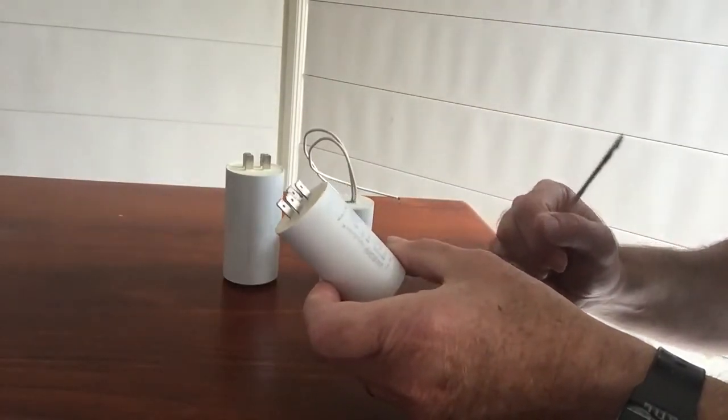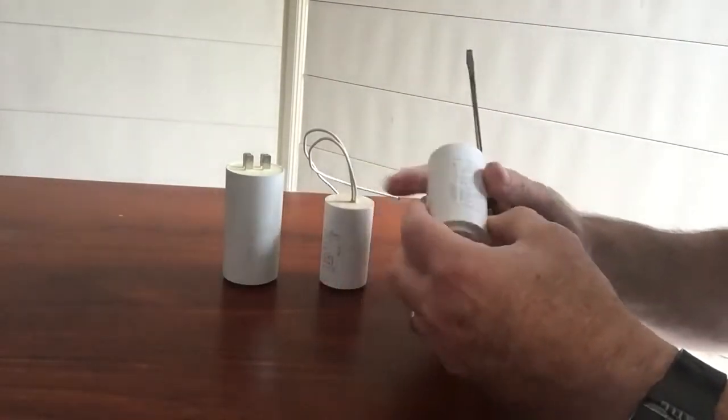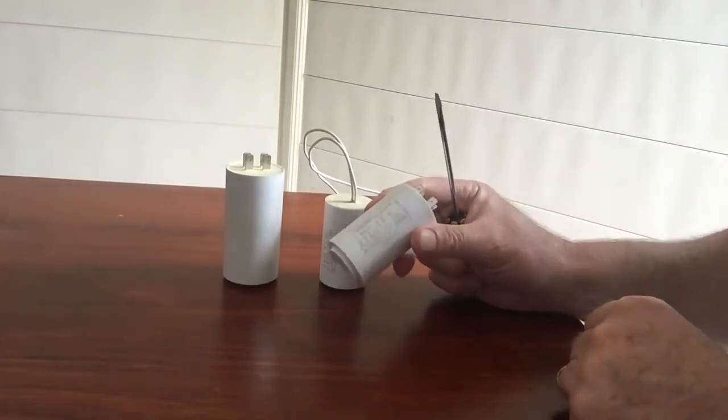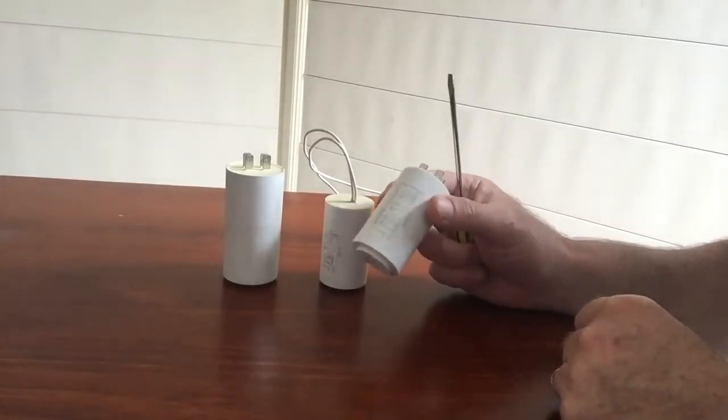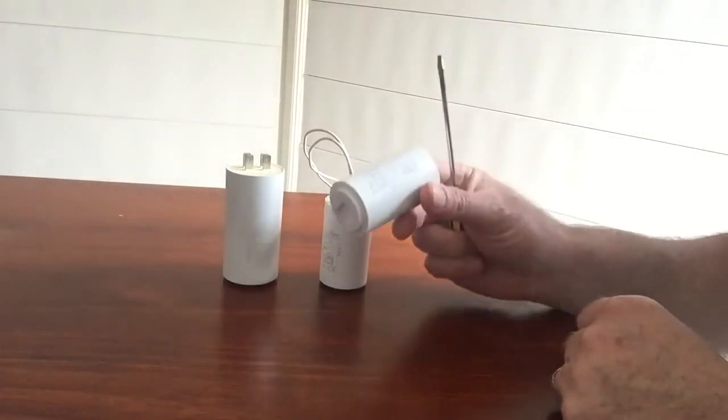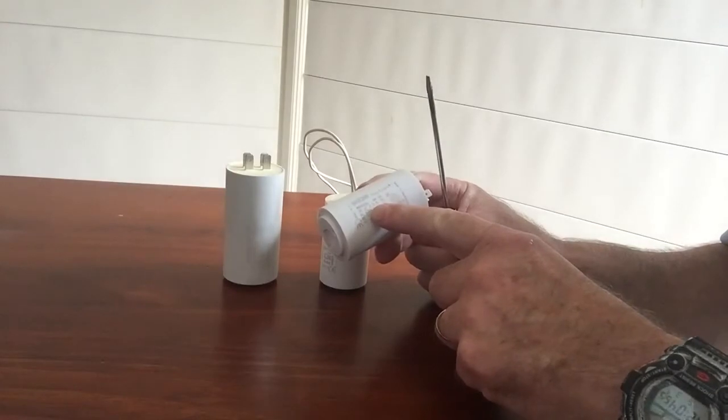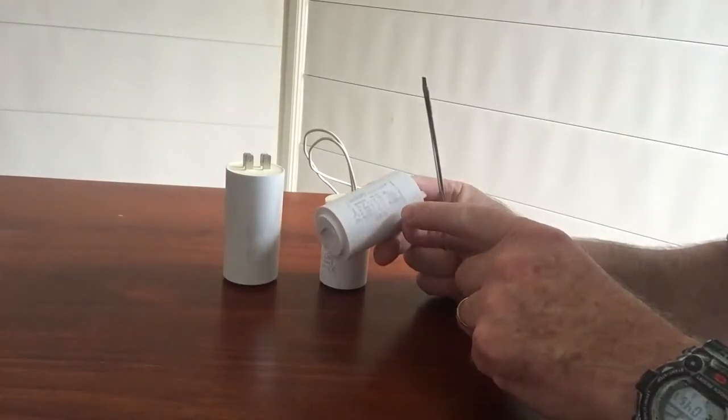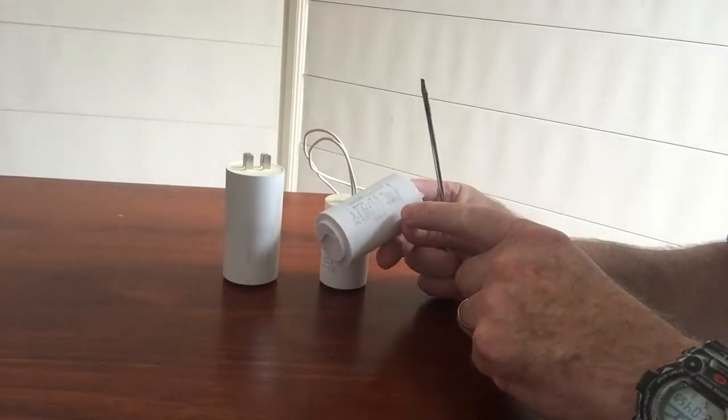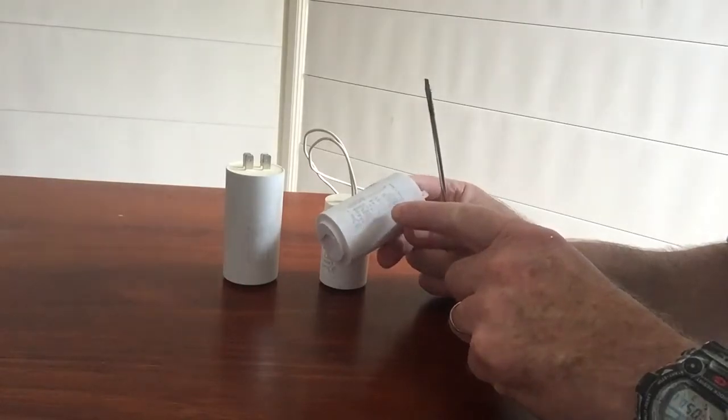Now there's a fair range of capacitors that can go in pool pumps. These are the common style - this is a 20 microfarad. Microfarad is shown by the symbol UF on the capacitor. The most important thing when you're replacing a capacitor is to look for the size. This one is 20 UF, which stands for 20 microfarad.